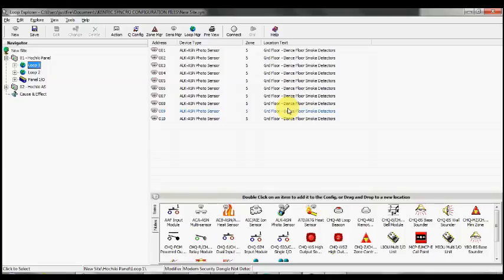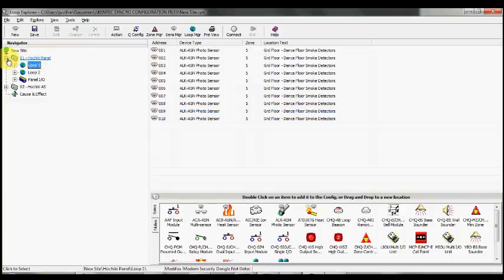These are smoke detectors. For this example, we're going to have these devices isolated when an input on this panel is triggered, which will effectively disable these devices so they can't respond to any activation. The first thing we need to do is set one of the default inputs on the Synchro panel to be a disablement type input.